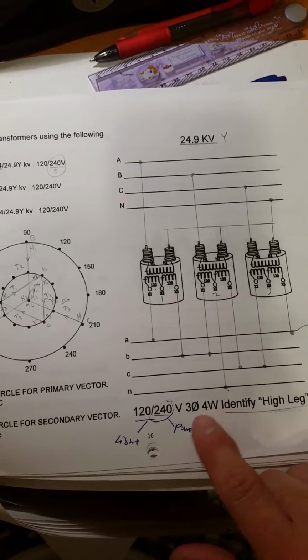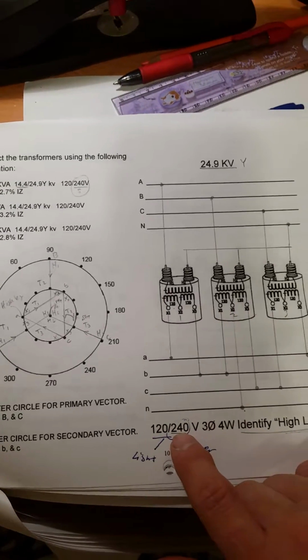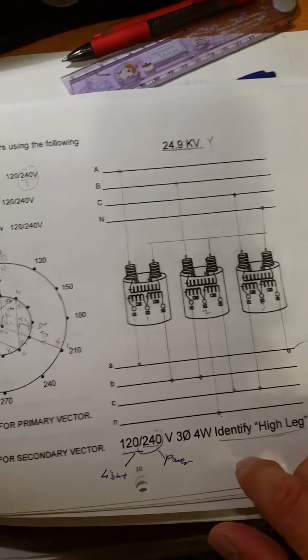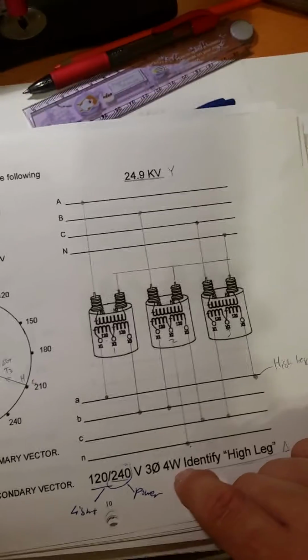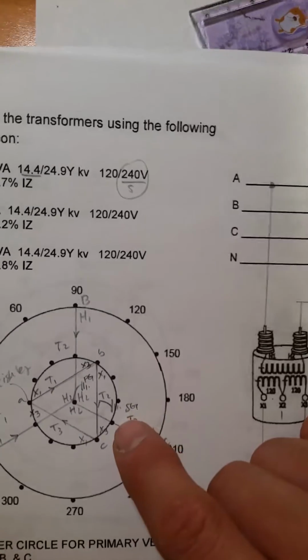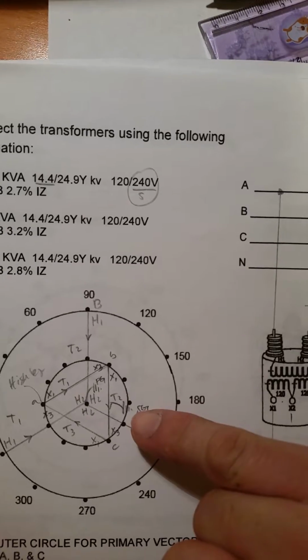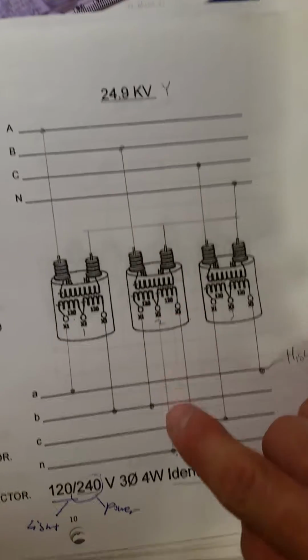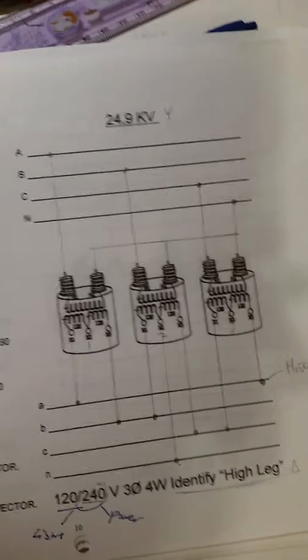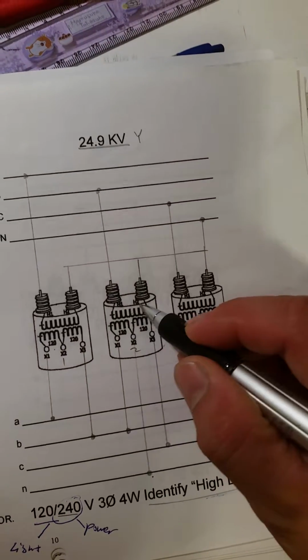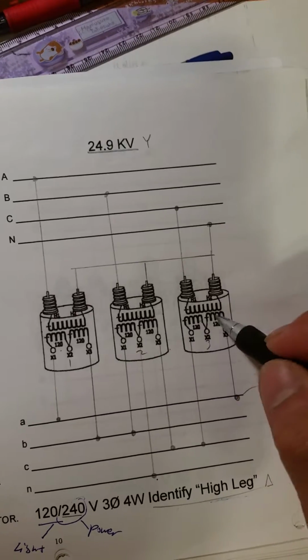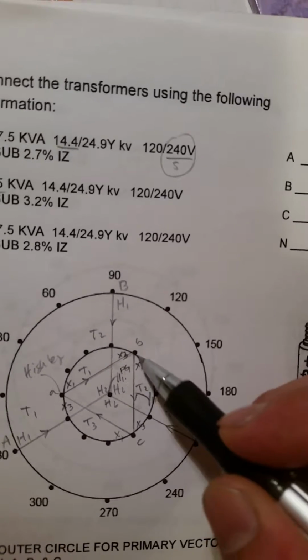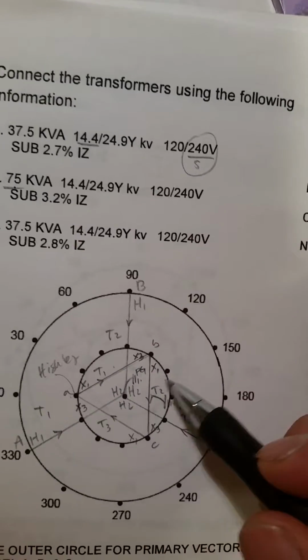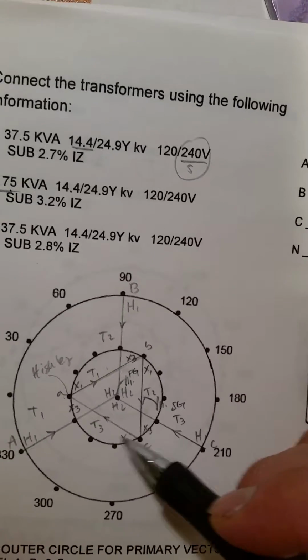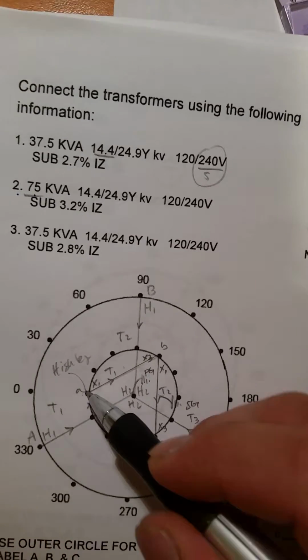Identify the high leg. This is the one with the 120/240, but it's a 3-phase 4-wire. How do you identify it? When you have your can right here grounded, 3 coils away, you're going to have a high leg. 1 coil away, 2 coils away, 3 coils - that's where you get the high leg. You don't have to go this way, you can go this way too - 1 coil here, another coil here, another coil here. That's 3 coils, and that gets you to high leg.